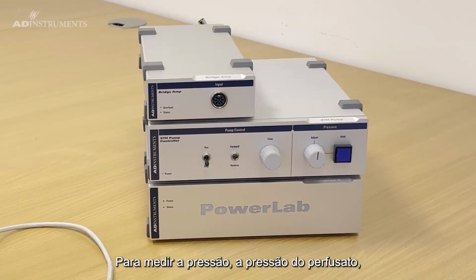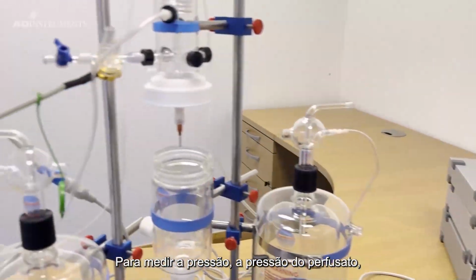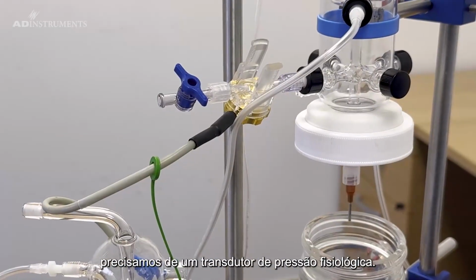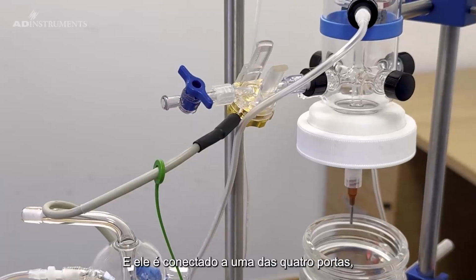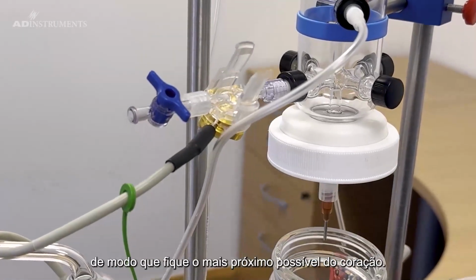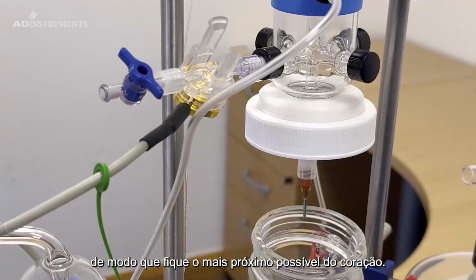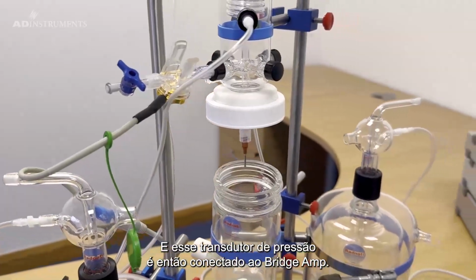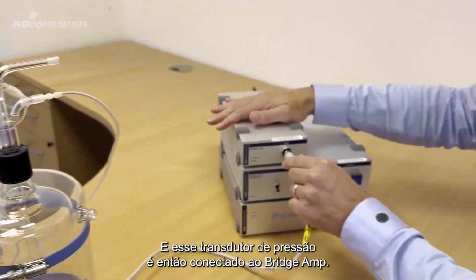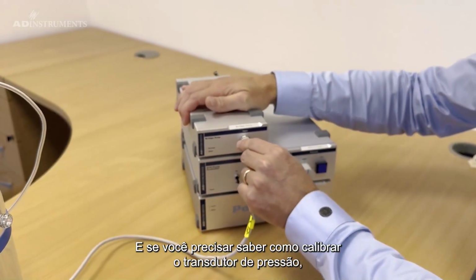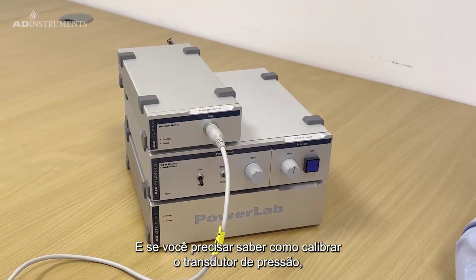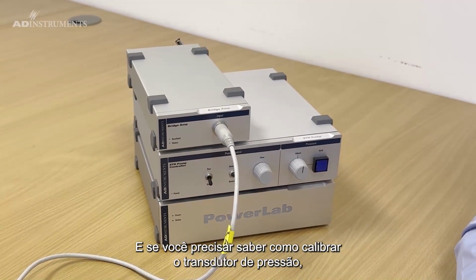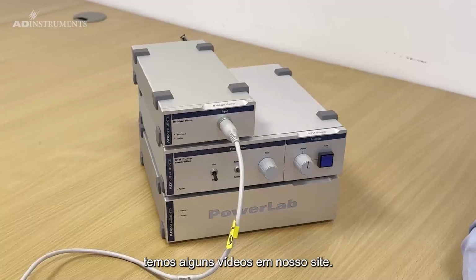hardware. To measure the perfusate pressure, we require a physiological pressure transducer, and this is connected to one of the 4 ports so that it's as close as possible to the heart. And this pressure transducer is then connected to the bridge amp. And if you need to know how to calibrate the pressure transducer, we have some videos on our website.